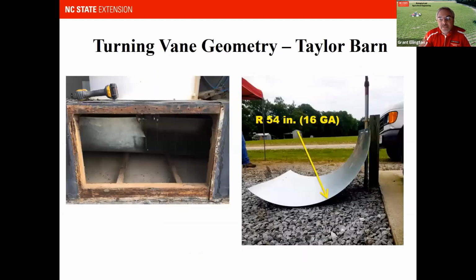This slide is showing just a couple of pictures of our turning vane geometry. And so the picture on the right is showing the actual 16 gauge sheet metal that we rolled into a radius of 54 inches. And then the picture on the left is showing it installed. This just happens to be at this particular location.